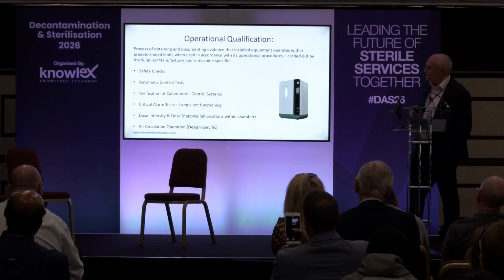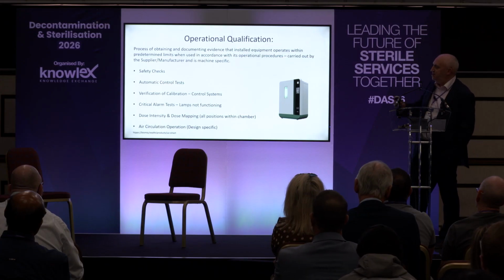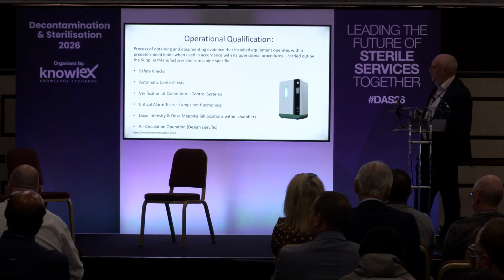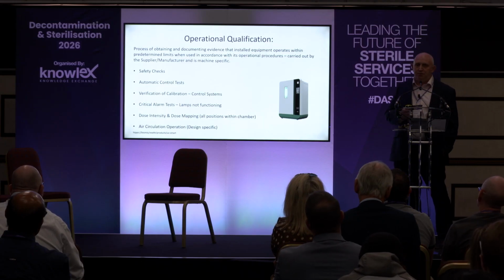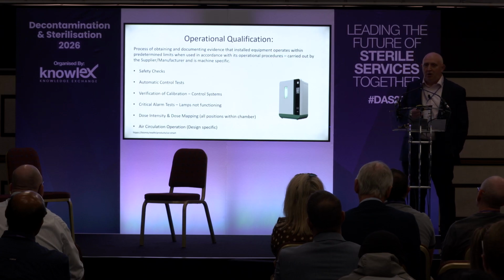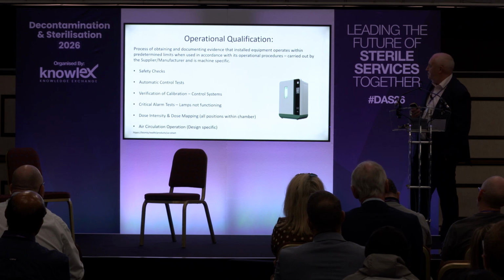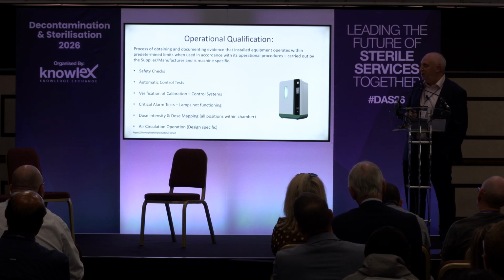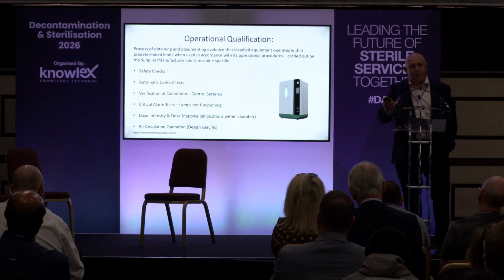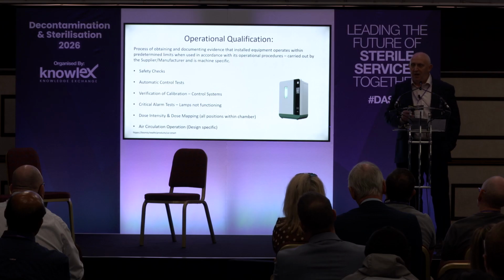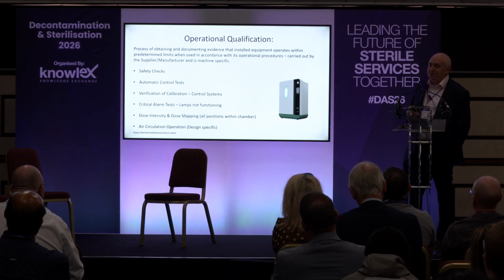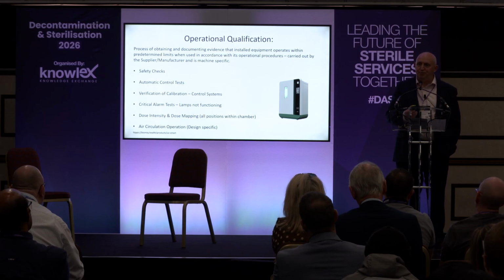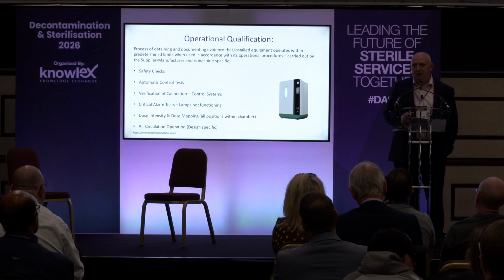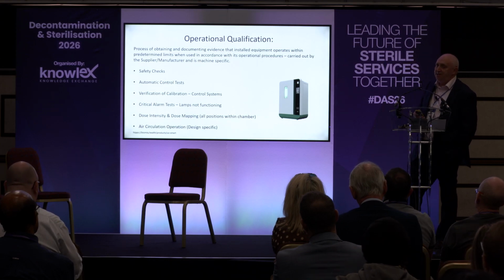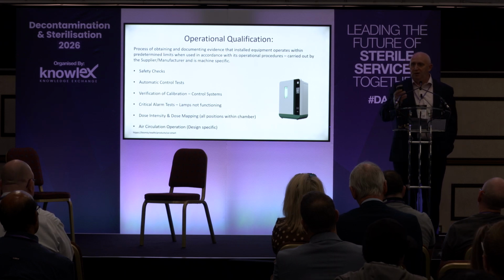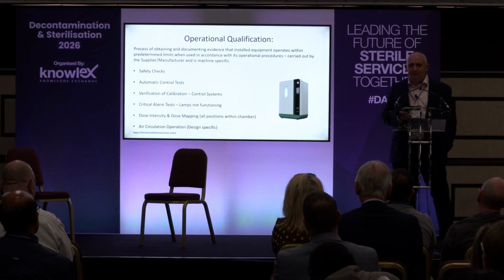Operational qualification. Again, we're repeating the safety checks. This is a typical format for any sort of decontamination equipment. We do the ACT, the automatic control test. We do a verification of calibration on the control systems. Yeah, if it's set at a control temperature, we need to make sure that control temperature is correct. Again, critical alarm tests. So if a lamp fails, it should pick that up. We must provide evidence of dose intensity and dose mapping. Yeah, so we need to be sure that everywhere in that chamber is exposed to the dose. And if there's any air circulation systems in there, it needs to confirm that that circulation is as per the type test information.